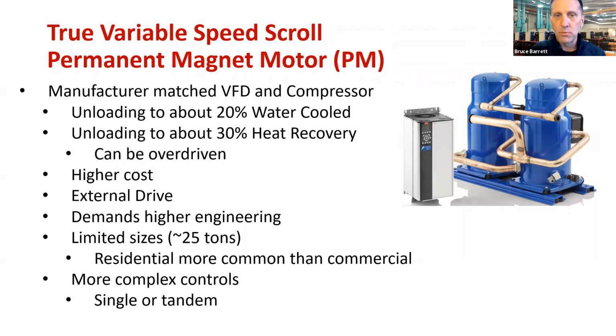Some new technologies, a 3.5 year old technology that we've been employing on scroll heat recovery chillers, is true variable speed compressors. It is a matched engineered drive and compressor. They can load very well, about 30% in a heat recovery environment. They can be overdriven, so they can get some extra capacity. You do have to mount that drive somewhere on the equipment, but it does give better part load performance throughout the operating range as opposed to on-off compressors.